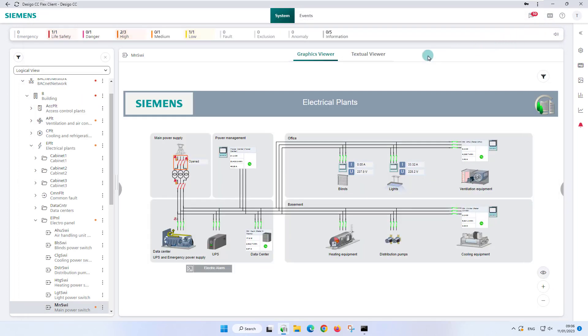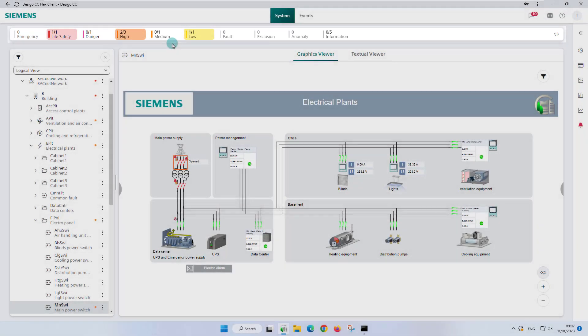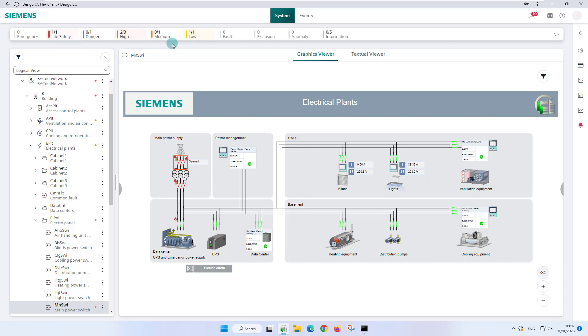Events occurring in the Flex Client application are grouped into categories that are color coded by severity and named accordingly, such as emergency, life safety, danger, high, medium, and so on. The summary bar provides an overview of the event lamps. The number of event lamps in the corresponding categories depends on the customer profile of the logged in user. For example, in chapter 2.7 logon with different users, we logged in with a user that had only the view of the discipline building automation, and therefore the number of event lamps in the summary bar consequently decreased.